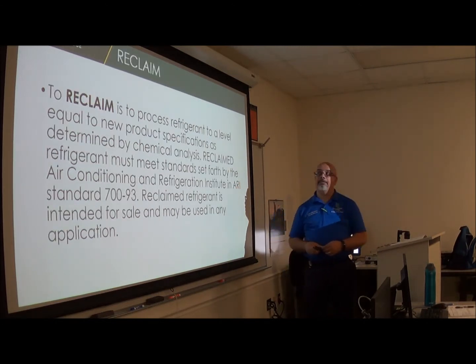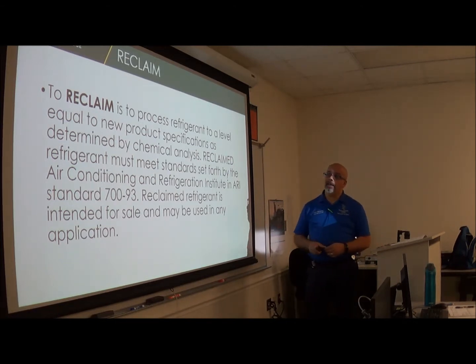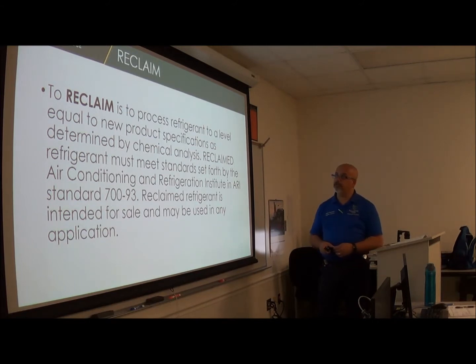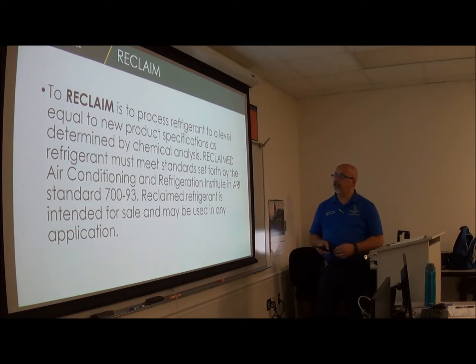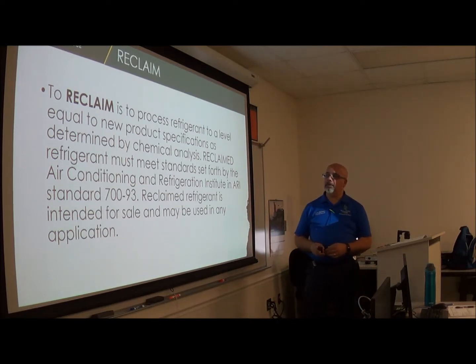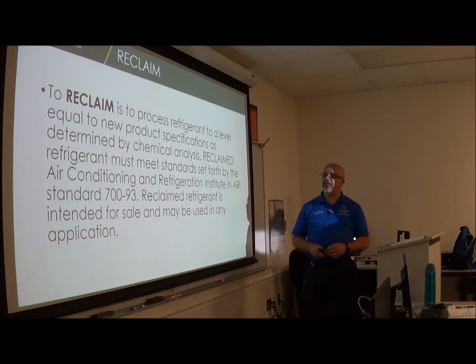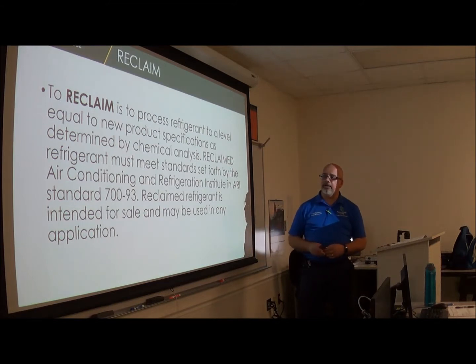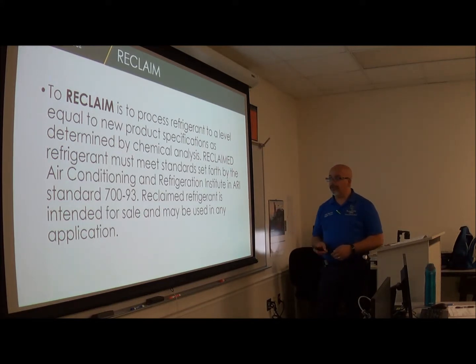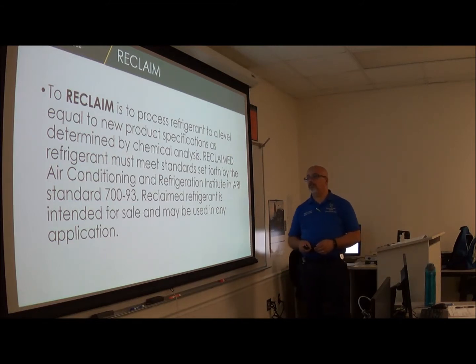To reclaim is to process refrigerant to a level equal to new product specifications as determined by chemical analysis. Reclaimed refrigerant must meet standards set forth by the Air Conditioning and Refrigeration Institute and ARI Standard 700-93. Reclaimed refrigerant is intended for sale and may be used in any application.